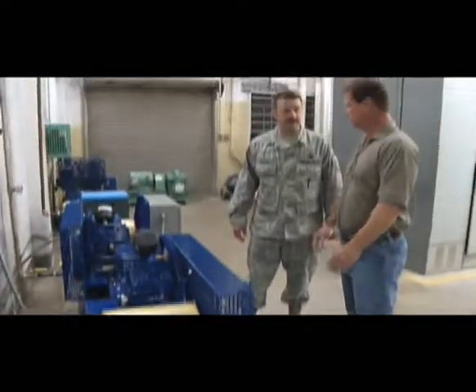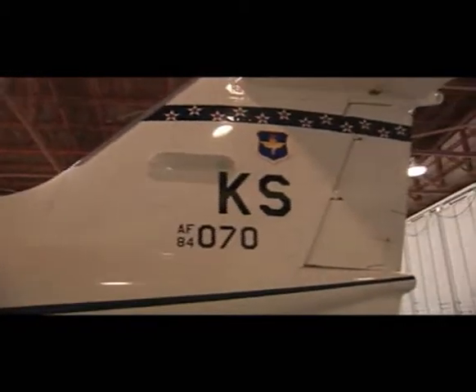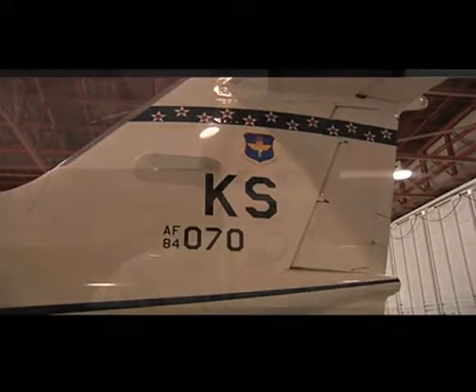We installed lock boxes on those thermostats to keep people from playing with the temperatures. Went from four coffee pots down to one coffee pot. I did find a major contributor, which was an air compressor that was cycling on every 30 seconds, running basically 24 hours a day, seven days a week, and who knows how long. Just Keesler pays for energy and it's over a million dollars — and that's a million dollars that could be going towards supporting that mission.